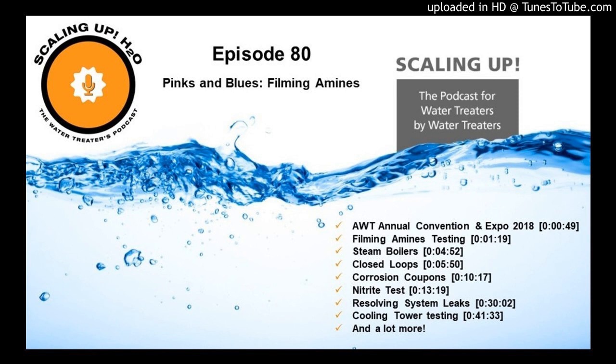If I have a pound of sodium molybdate and I have 1,000 gallons of water and I put that 1 pound of sodium molybdate in that 1,000 gallons of water, I will test 120 parts per million of sodium molybdate. If I had sodium chloride, the same thing. Well, in this case, I have sodium nitrite, probably your favorite closed loop mild steel inhibitor.